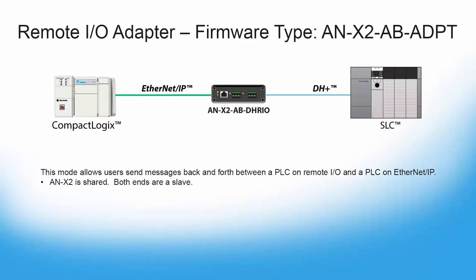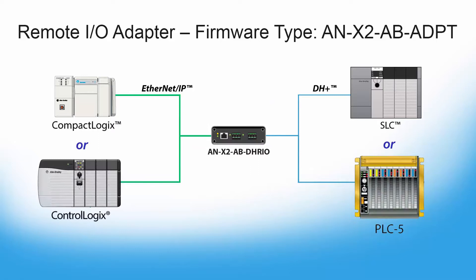Finally, we have the ANX2ABADPT, the Remote IO Adapter Mode. This is primarily used for messaging between PLCs on RIO and PLCs on Ethernet IP. In this mode, the ANX2 is a slave on both ends, appearing to the PLCs as a remote rack.